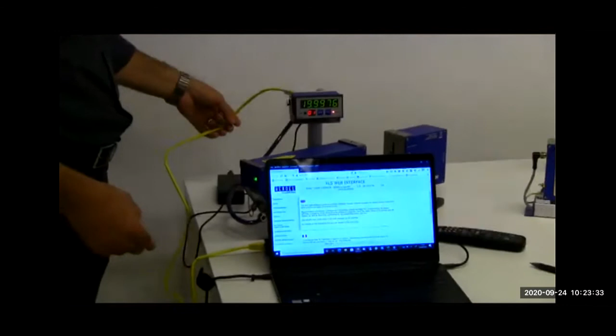Here there are outputs for the light, or inputs for an external switch to give the start and stop of the measurement, and it can simply be connected to a PC using the Ethernet socket in the rear of the display. You connect simply using an IP address that is derived from the serial number of the laser sensor.